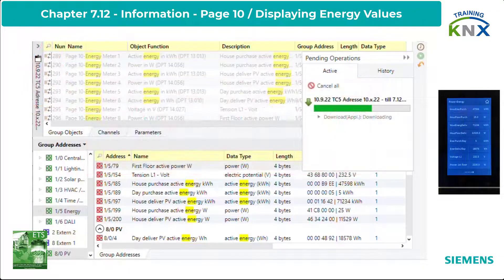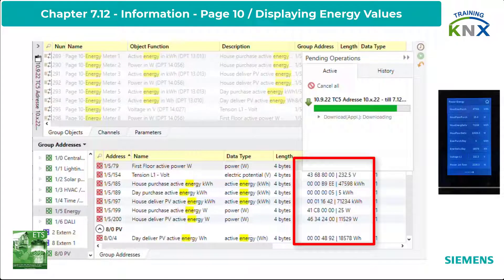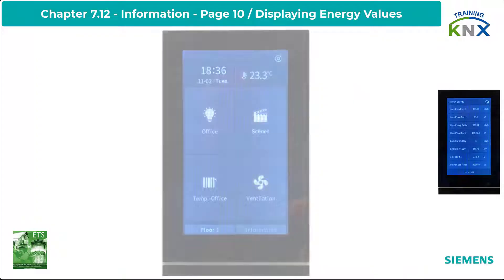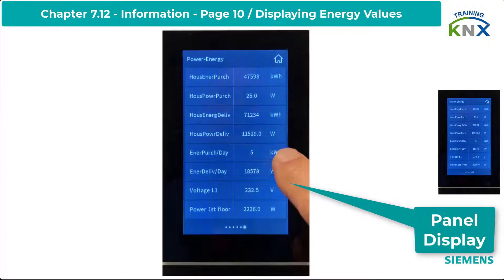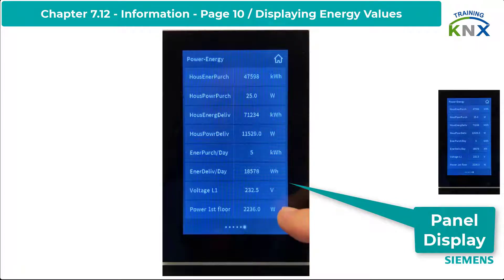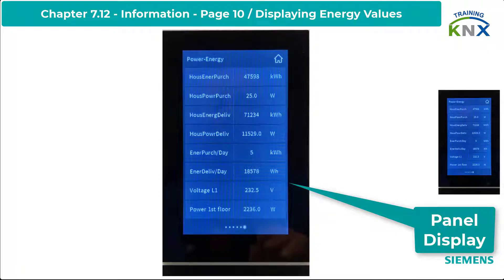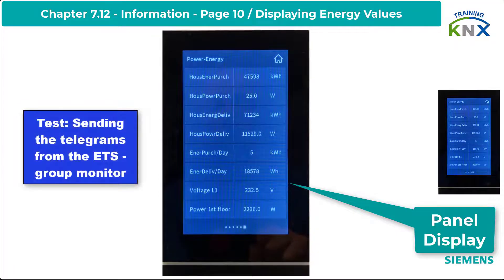Now the download, and here the display of the data. It is a simple list with the 8 entries, one below the other. If you want to test the whole thing yourself, just send the corresponding telegrams with simulated values to the TC5. The ETS can also send these manual entries correctly coded with the appropriate DPT assignment.